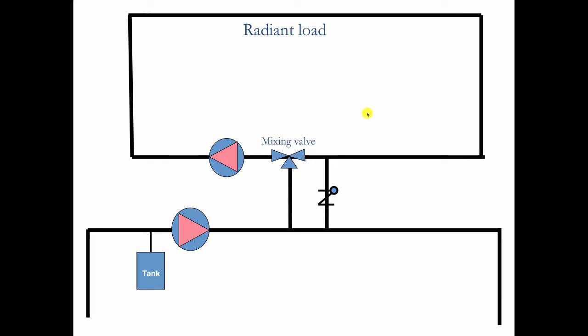This is done with a three-way mixing valve. We see these all the time. This is the primary loop over here with the compression tank here. The secondary circulator is using this connection and the common piping as its compression tank, so we're pumping away from that.